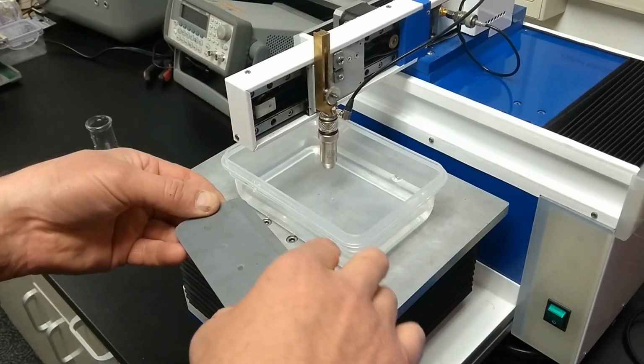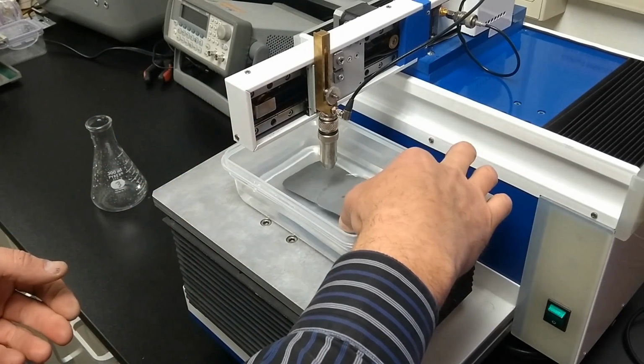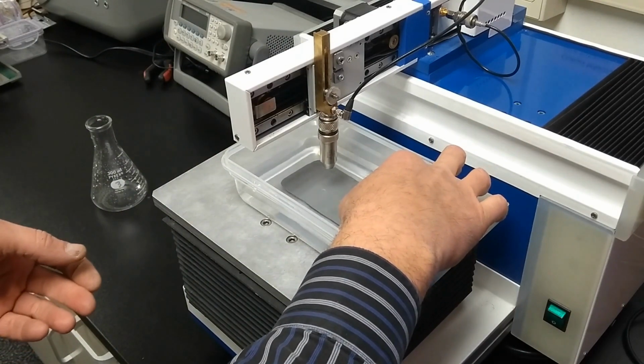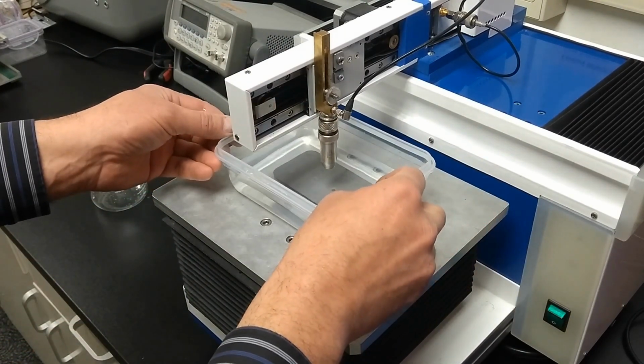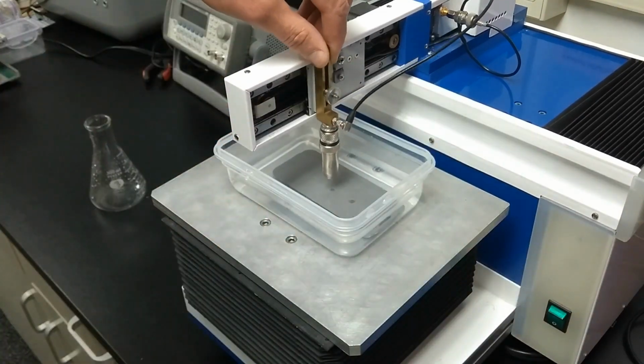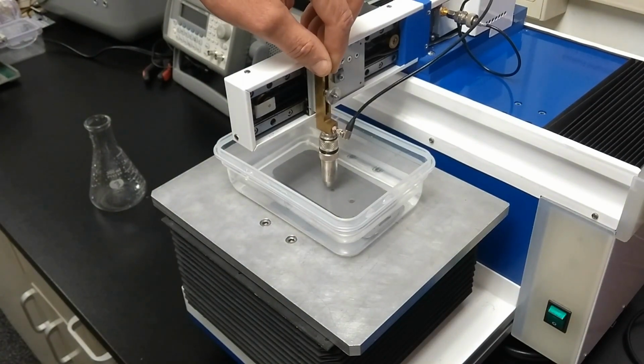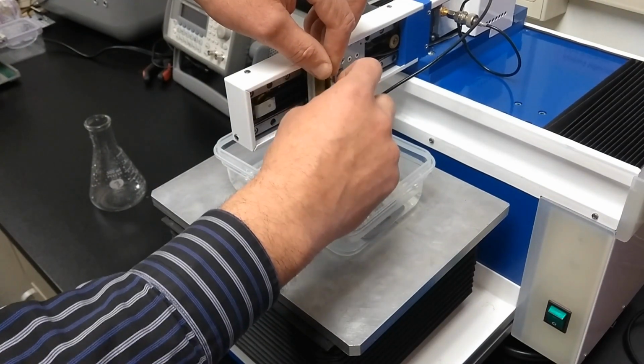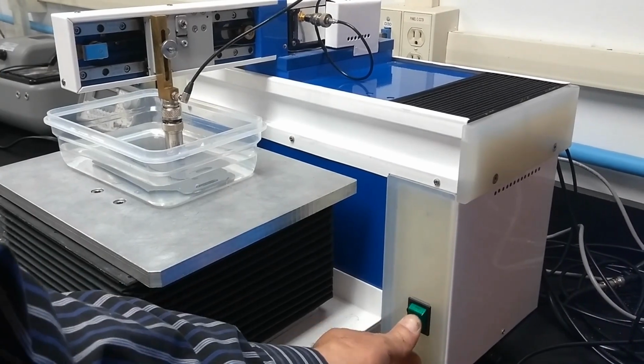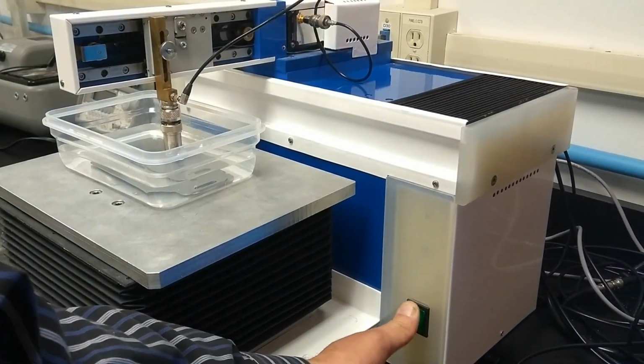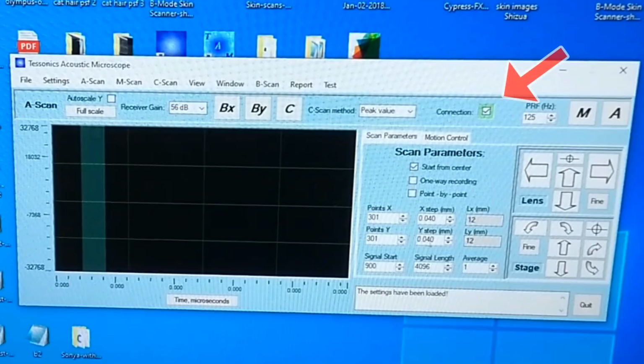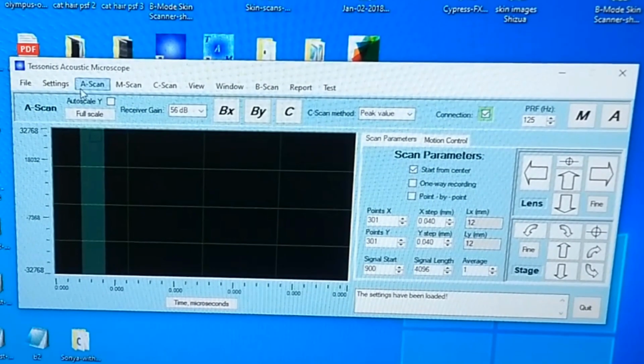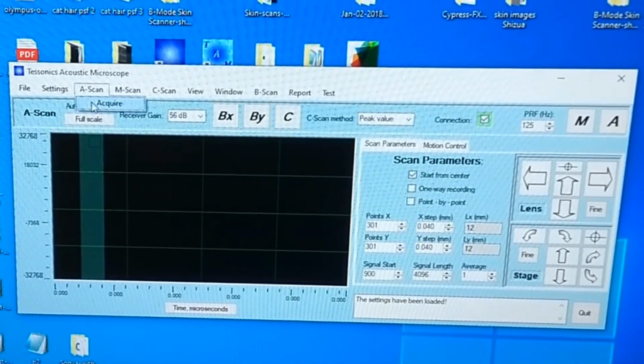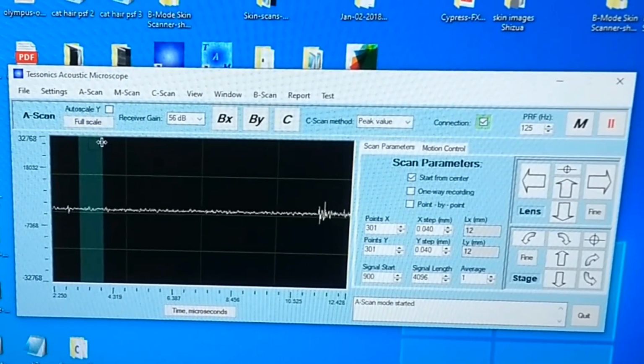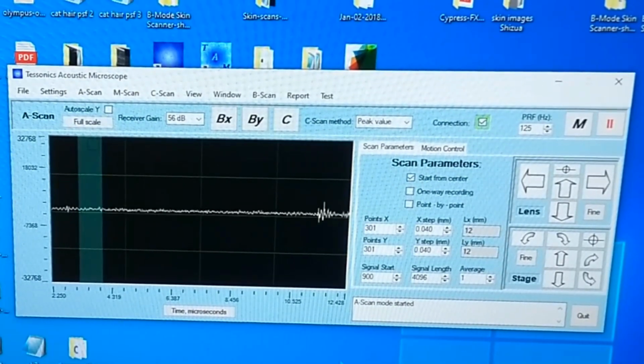The sample is placed into the immersion container and should be covered by water with a depth a little more than the focal length of the transducer. The transducer is then lowered down until it touches the water and is fixed in position. The scanner is turned on and the control software is launched. The green light indicates that a connection has been established between the scanner and the computer. Pressing A scan, then acquire, will bring up the real-time A scan provided by the transducer.